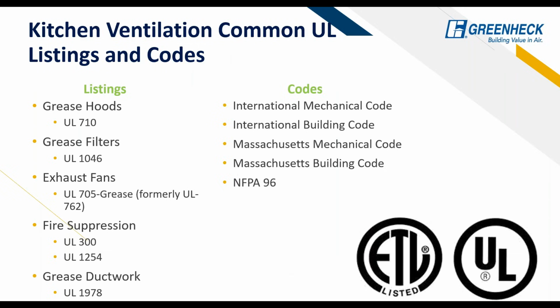So some common UL listings and codes, I'm not going to go through all of these, but the main ones are the grease hoods with UL 710, as well as the exhaust fan UL 705-grease. That was formerly UL 762. So you might still see reference to UL 762, but they have merged it into UL 705, and they call it UL 705-grease. And then for fire suppression, UL 300, and then grease ductwork has its own codes as well. And then you'll also see some reference to the International Mechanical Code, the IMC, specifically referencing the airflow rates for these hoods. So we'll get into airflow rates as well.